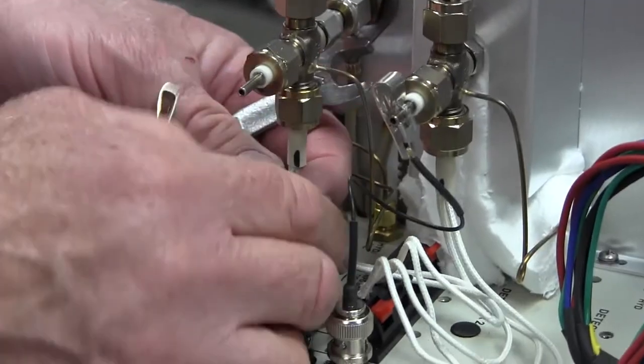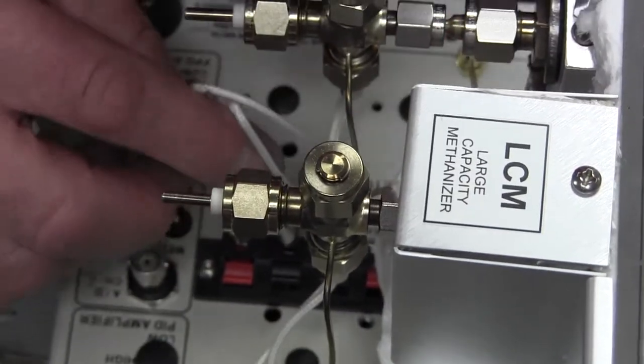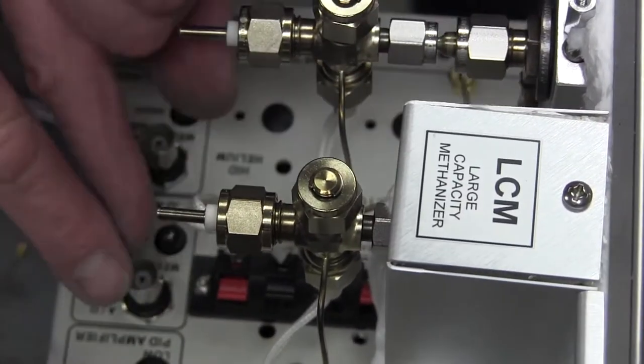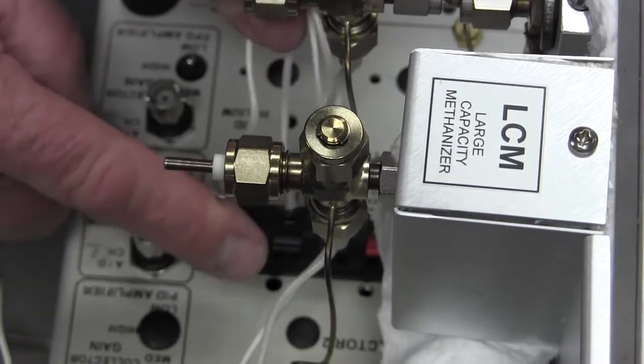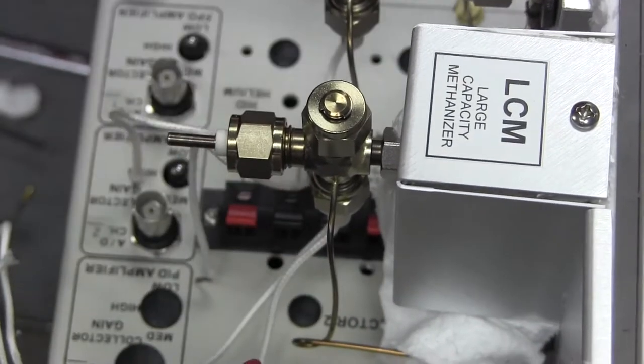It shouldn't be on super tight, it doesn't need to be, there's no pressure. So it should be easy to just spin off with your fingers like that. Then there's something called an igniter, which is the thing that's hot inside the FID that lights the flame automatically.